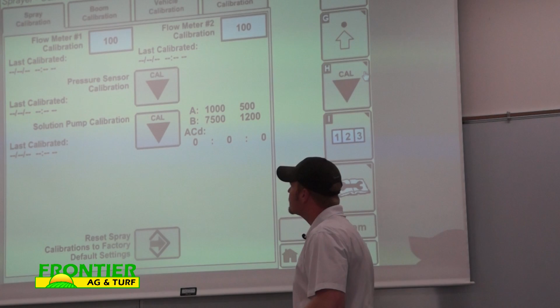Go through calibrations here real quick. Soft key H. So I have my calibrations in here. These should all stay in here over winter. They shouldn't change. Flow meter cal, just double check. There should be a tag on each flow meter that gives you a calibration number that you got to plug into the display. This is going to give you the ability to get the most accurate GPM. They're all tested at factory, given a cal number. We got to tell the controller what that cal number is so it can make the calculation.